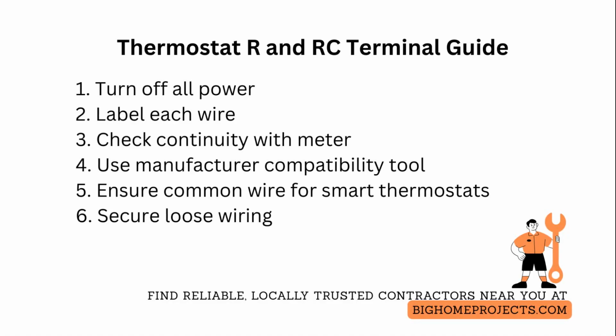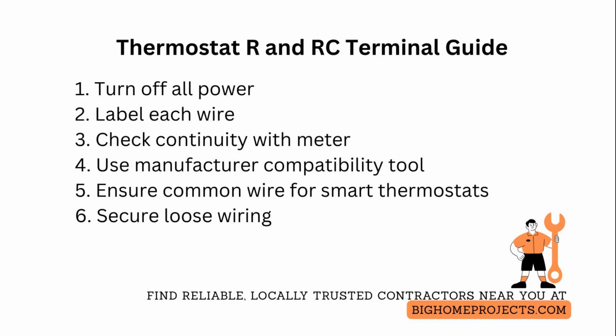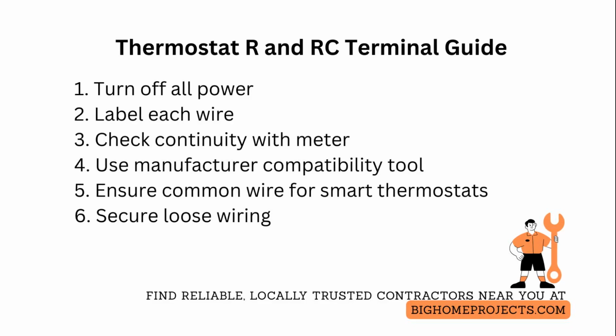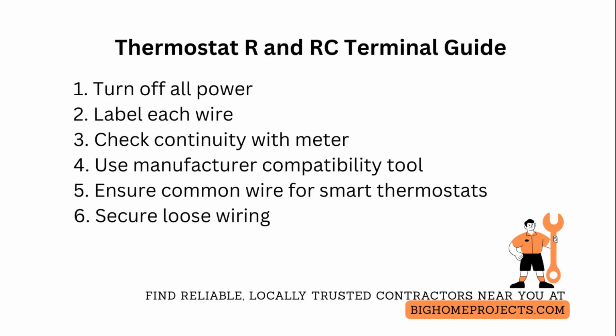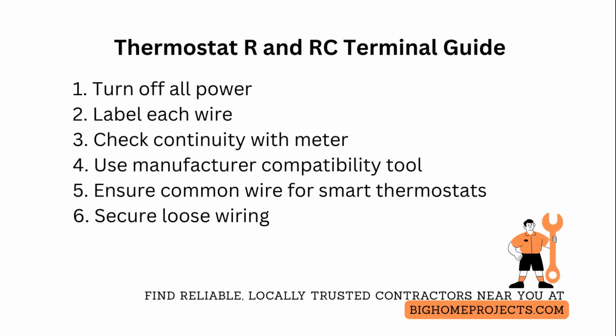If your thermostat has separate R and RC and you have only one furnace or air handler, leave the jumper in place and wire the cooling call to RC and the heating call to R so both circuits share the same 24-volt feed. If you have two separate systems, for example, a boiler for heat and an air conditioner with its own transformer, remove the jumper and wire the boiler's transformer hot to R and the air conditioner's transformer hot to RC to keep the two transformer secondaries electrically isolated. Never tie two transformer outputs together, or you will short them and likely blow fuses.